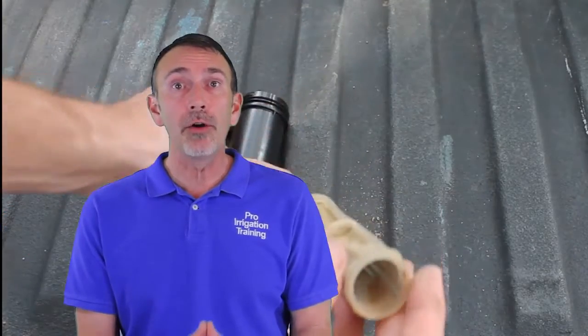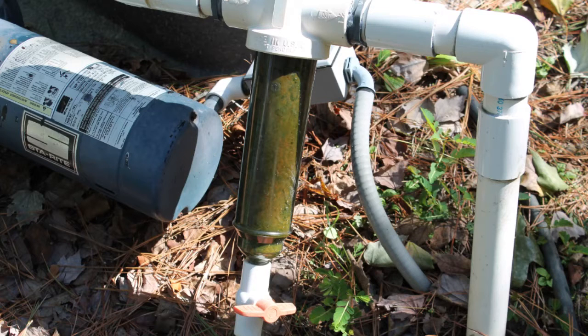It doesn't do you any good to install a filter on a system if the owner of that system or the manager of that property never cleans the filter. In fact, it can even damage some of the other parts of the system because the flow gets reduced by the buildup of particles in the filter itself. So especially with pump systems, be careful with that. So it's better to even not use a filter on non-drip systems if there's no maintenance plan or there's no chance of getting these filters cleaned out several times a year.